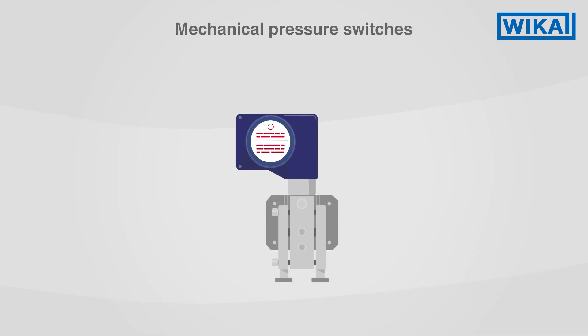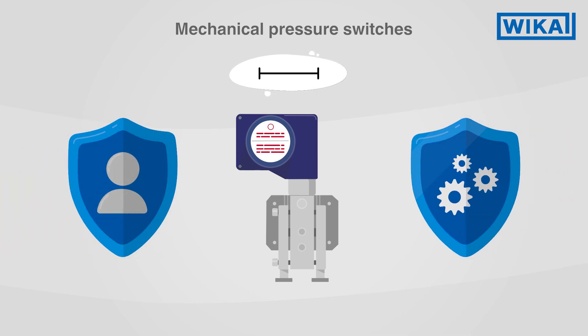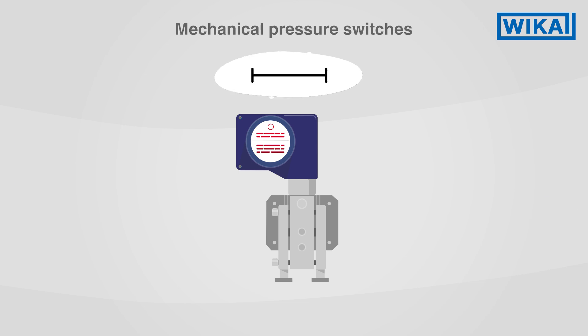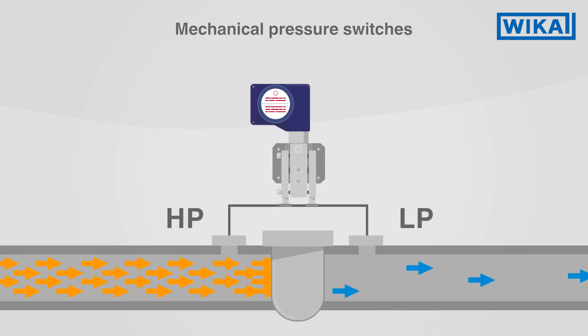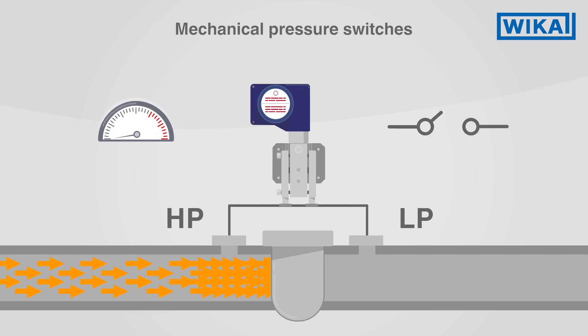Mechanical pressure switches are used to keep the pressure within a predefined span. In this way, people and plants are reliably protected. In the example of filter monitoring shown earlier, differential pressure switches can react accordingly or transmit signals as soon as a certain value is exceeded or fallen below.